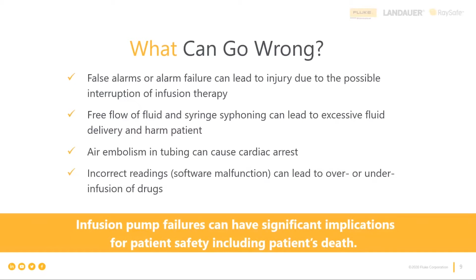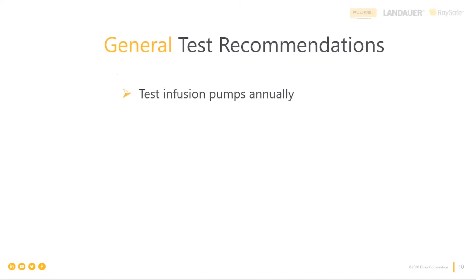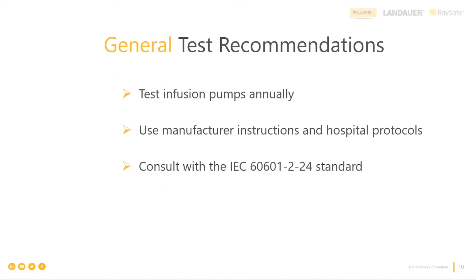Here we have a few very general test recommendations. Before we dive deep into the test procedures and test methods, I would like to give this high-level overview of the recommendations that we have for infusion pump testing. First of all, you have to test your infusion pumps annually, and we will talk about why in a few moments. You need to use manufacturer instructions and hospital protocols to follow the procedures. You need to consult with the standard, the IEC 60601-2-24. And you have to document the results of your test for traceability and compliance.